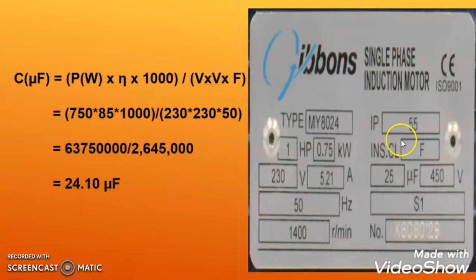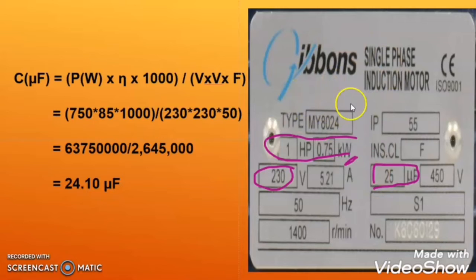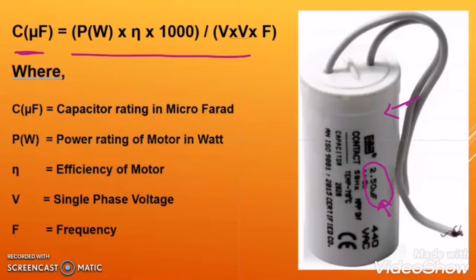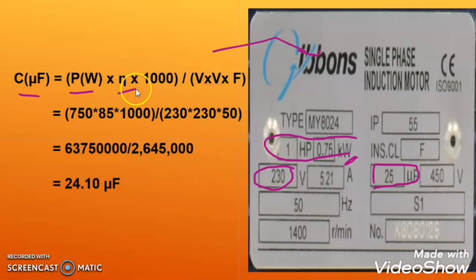Now let us take another example. Here you can see the motor rating is given as 1 HP or 0.75 kilowatt, and the voltage is given as 230 volts. The microfarad value is also given on this motor's nameplate — this induction motor requires 25 microfarad. But let us calculate using the formula to verify: C = P × efficiency × 1000 ÷ (V² × f).